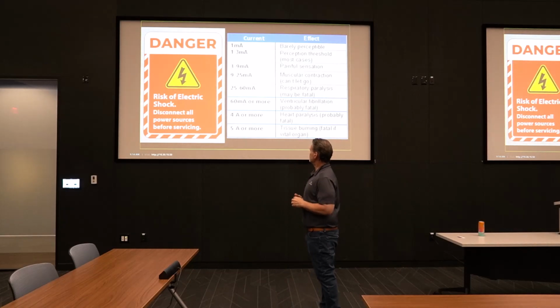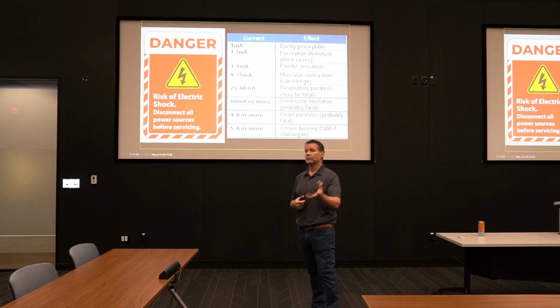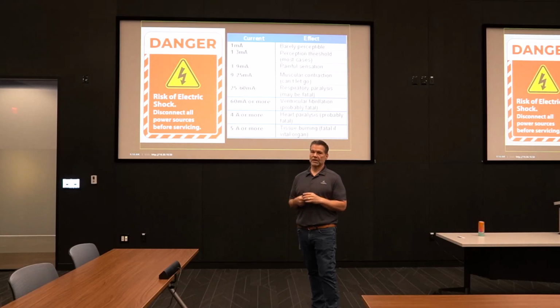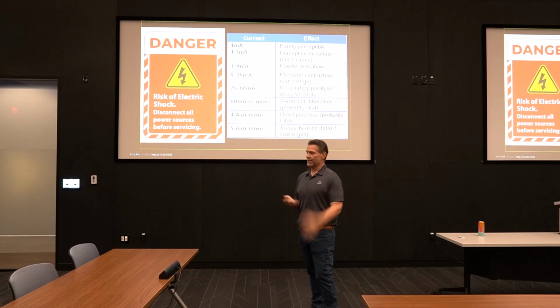Once you get up to 60 milliamps, that's ventricular fibrillation. That's when it becomes possibly fatal. But you see there, we haven't even reached an amp yet, and we're already at a spot where it could be fatal. And then at 4 amps, if you're not released from that circuit, chances are it's going to be fatal. So it takes very little amperage to kill you, very, very small amounts.